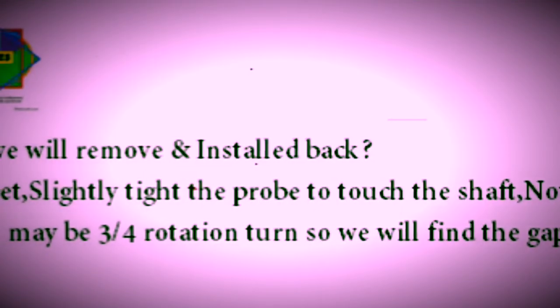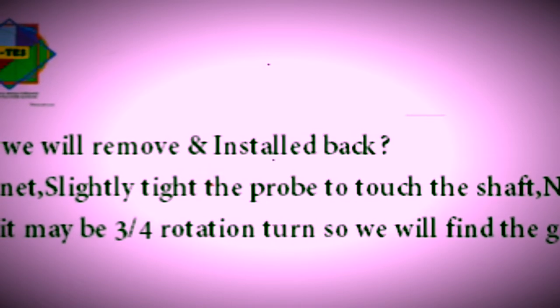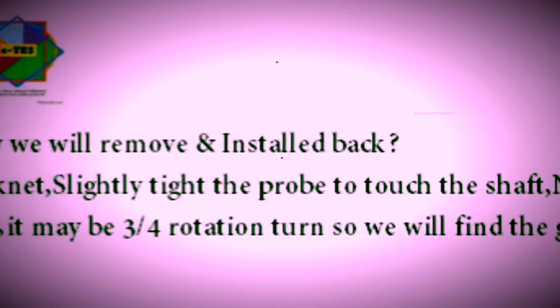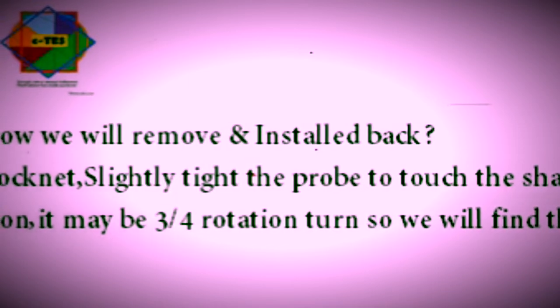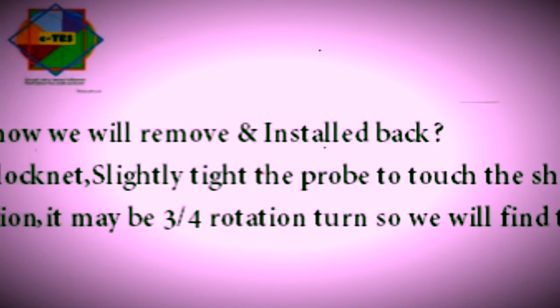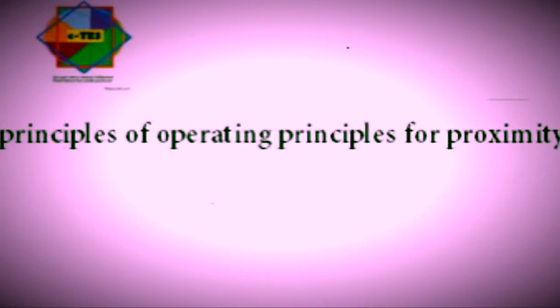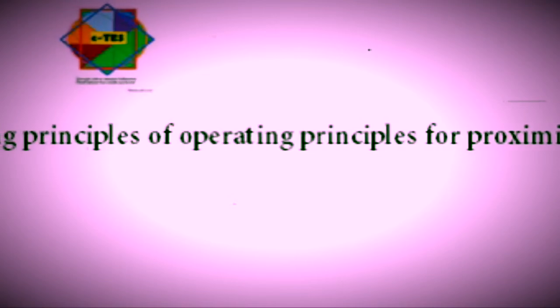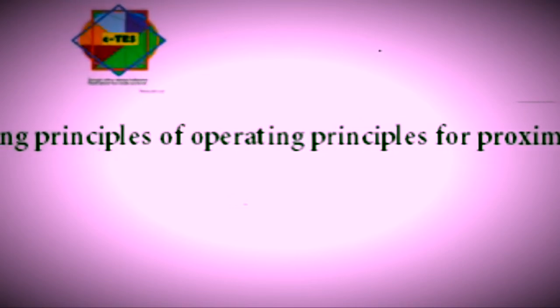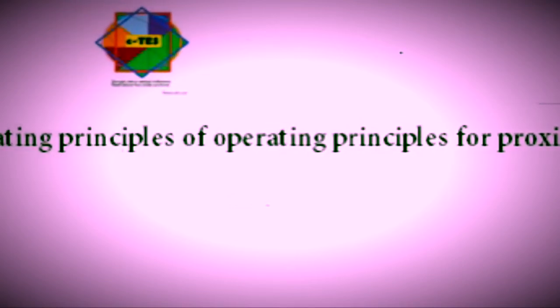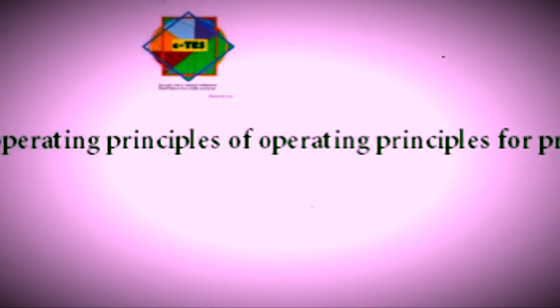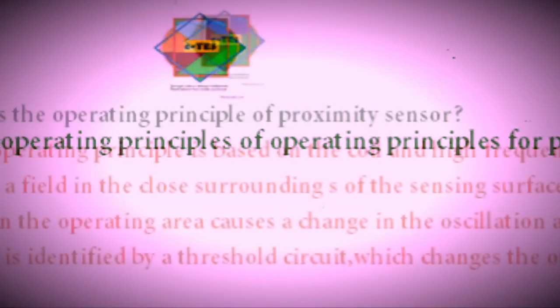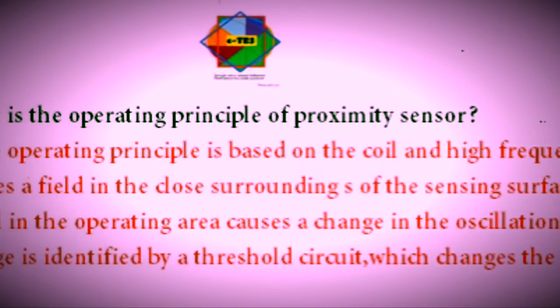In maintenance, how we remove and install the probe: we should loosen the locknut, tighten the probe to find when it touches the base, and note how many turns it takes to reach that position. This is the easy type of maintenance.